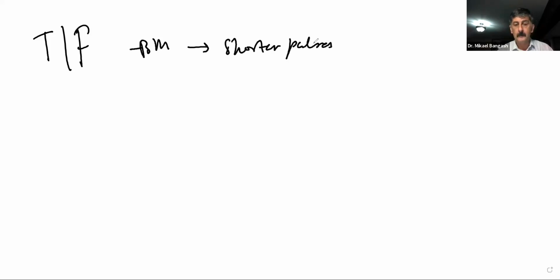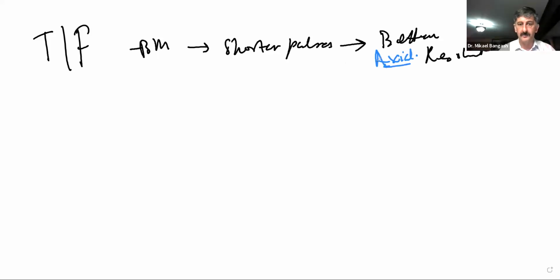Clear? And what that shorter pulse is going to give us is what we'll call a better resolution. It's actually not quality. To be more specific, it is going to give us a better axial resolution, because your axial resolution is determined by how short or long your pulse is.